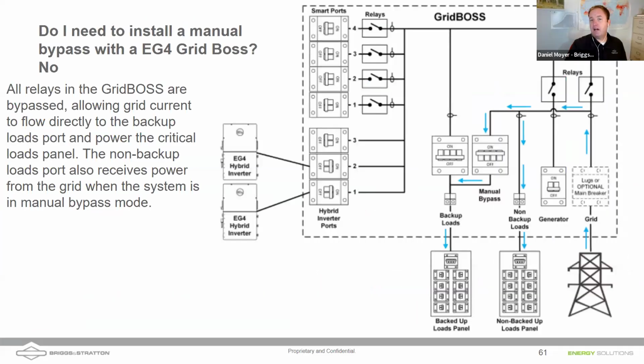Talked about this already, but I always like the idea of a manual bypass on energy storage systems. It allows you to service the system. If it's broken, it allows you to bypass it. And having that manual bypass is a great feature. There's two large breakers inside of this Grid Boss, and there's a breaker interlock kit that allows only one of these to be turned on at a moment, which allows you to bring in grid, flow down, and flow into the backed up loads panel. And if you look carefully at this diagram, it also continues to feed any of the non-backed up loads panels as well.